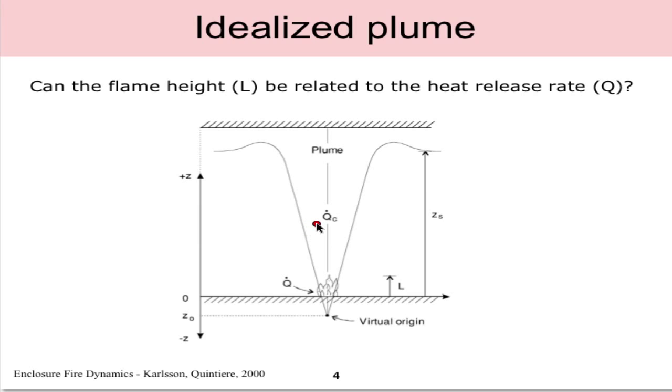We'll notice Qc which is the convective heat release rate denoted here whereas Q is denoted here for the total heat release rate and we'll see why that's important in a second. One other thing to note in this diagram is that the virtual origin or the point source is located below the floor and this is because if we have a finite burning area at the floor surface the virtual origin of the inverted cone will actually exist below the floor and the cone expands upwards to match that burning area.